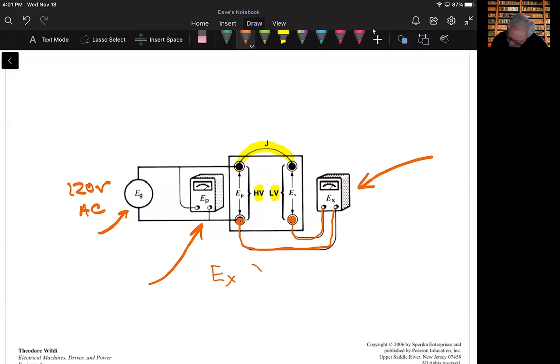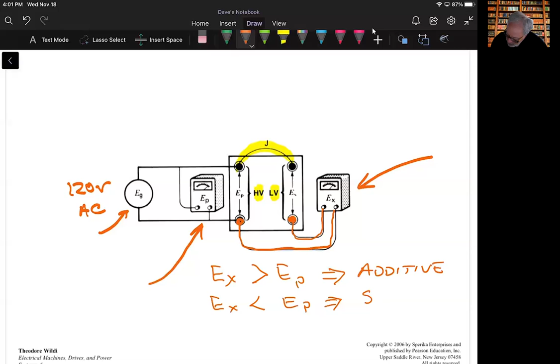Now, based on our configuration, if E sub X gives a higher reading than E sub P, then we're looking at additive polarity. Which also means if E sub X is less than E sub P, we're looking at subtractive polarity.